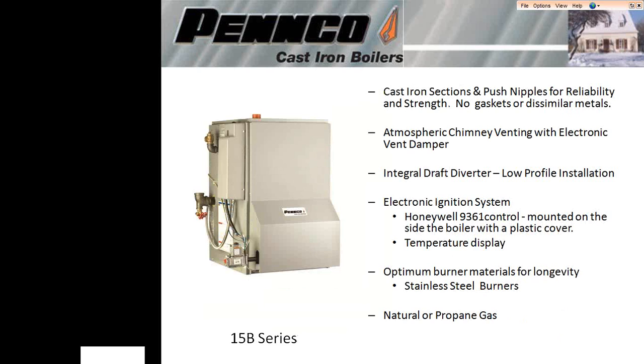So as you can see by the 15B, it's also a low-profile boiler. It does not have an integrated flue collector that the DXL does. It's still low profile because we have an external draft hood that will hang off the back of the boiler. That is a different design and engineering and manufacturing process, and that allows us to save a little bit of money. Additionally, we're not using the hydro-level hydrostat operating control.